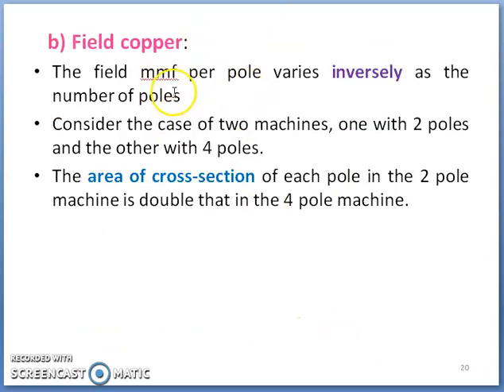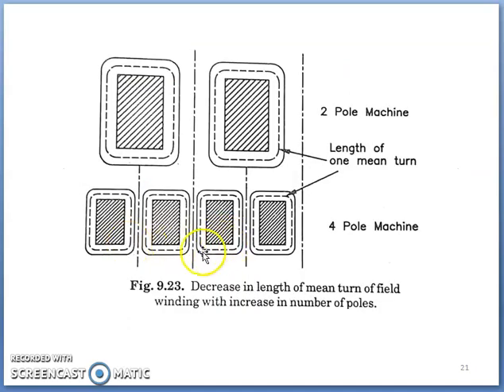Coming to field copper: the field MMF per pole varies inversely as the number of poles. If the number of poles is increased, then the field MMF per pole will reduce. Because of that, the cross-sectional area of each pole in a two-pole machine will be two times that of a four-pole machine — it is double because the flux per field MMF per pole is less for a four-pole machine. Hence, a two-pole machine requires more cross-sectional area to handle that flux flow. This image shows what happens to the length of the mean turn with increase in number of poles — the mean turn length for a two-pole machine is more than for a four-pole machine.